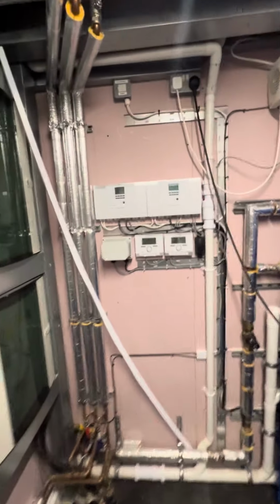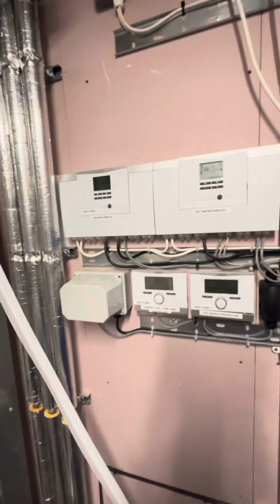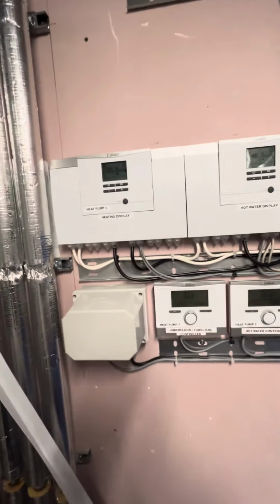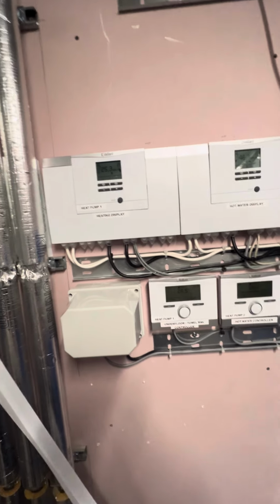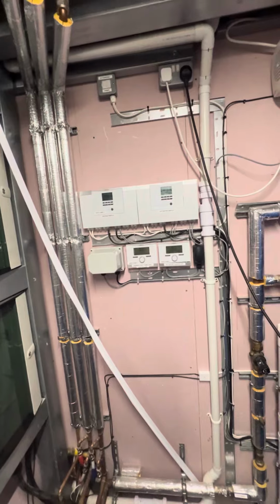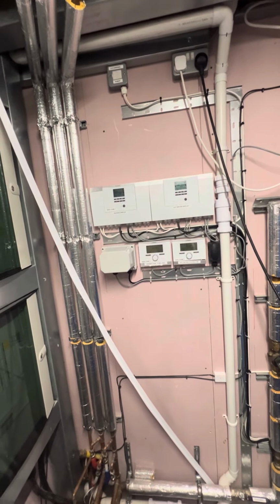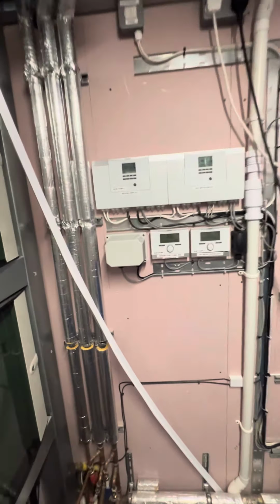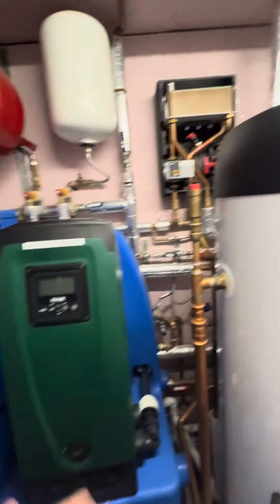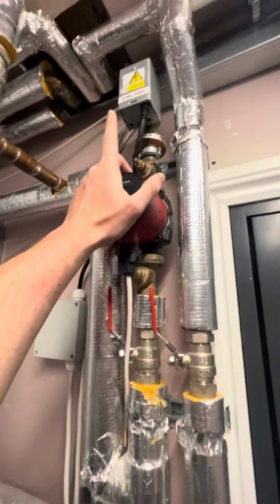So the first thing I did here was I checked the commission settings and the heat curves. I could see that the efficiency, we were only getting a COP of 3 when normally we get a COP of 4 on these systems, but thankfully I didn't install it, didn't design the system, but we are here to improve it. So what I noticed was the heat curve was on 1, which is really high for underfloor heating throughout, and I can only presume it was that high because of this towel rail circuit here.